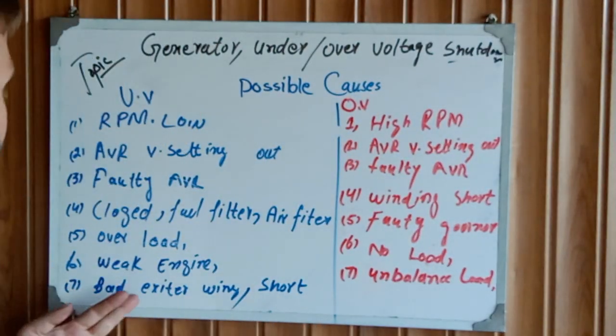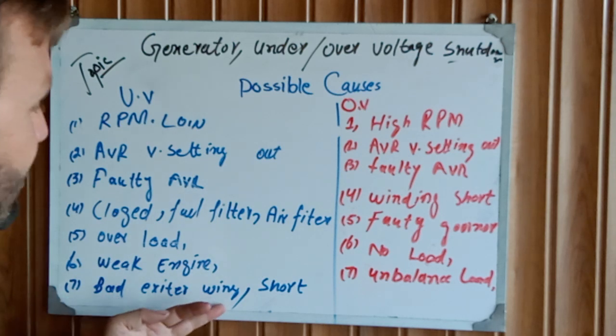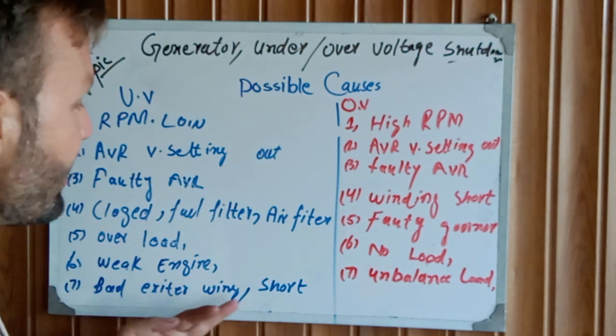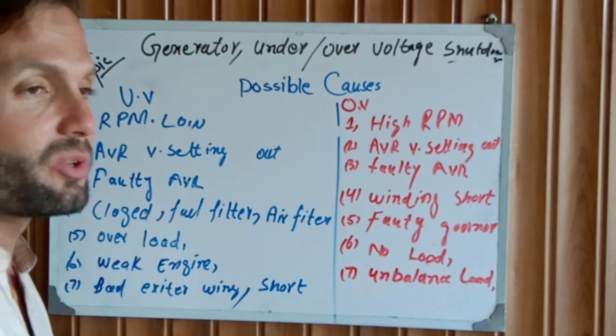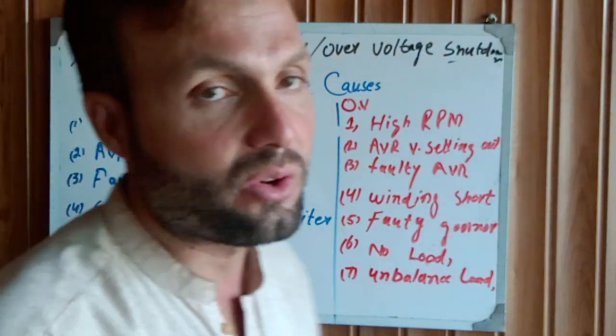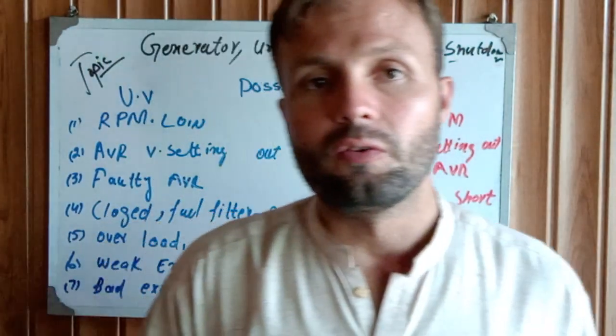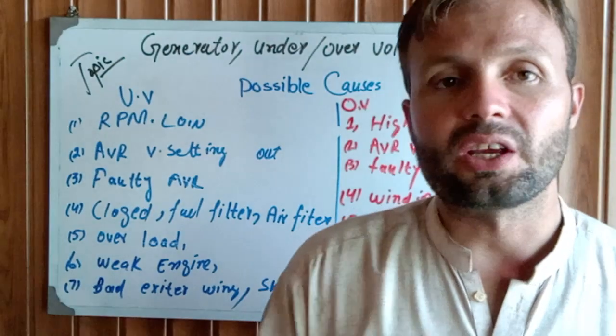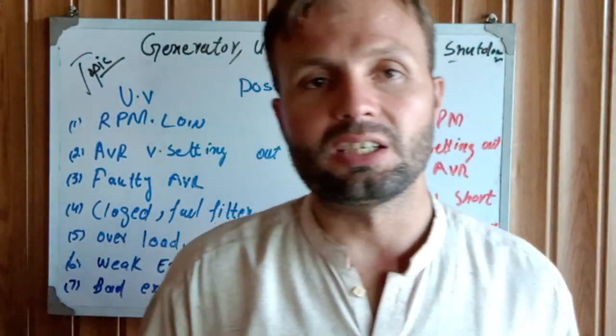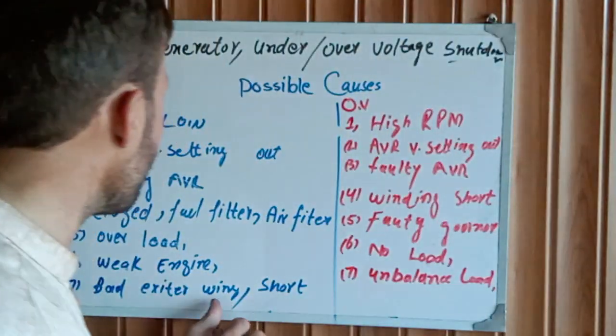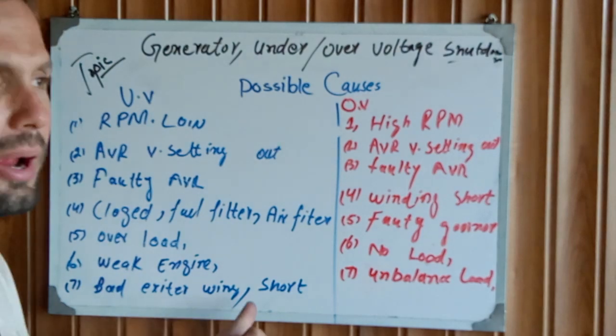The last possible cause for under voltage is a defective excitation winding or a short in the excitation winding. The alternator has a separate excitation winding which works for the excitation system of the alternator. When the excitation winding is shorted or bad, this causes under voltage.